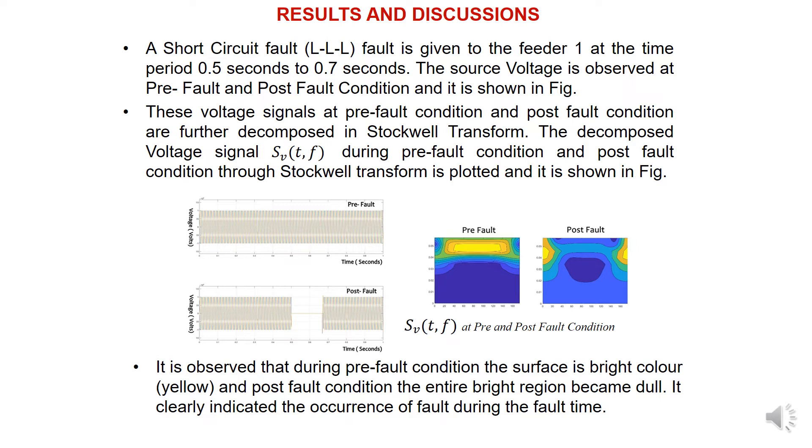Similarly, these voltage signals at pre-fault and post-fault condition are further decomposed using Stockwell transform. You can see the time-frequency responses of pre-fault and post-fault conditions. In the pre-fault condition time-frequency response, you can see the yellow color represents the healthy condition. After fault, you can see the yellow bright color changes into blue color. This is the post-fault condition which indicates some fault occurred here.